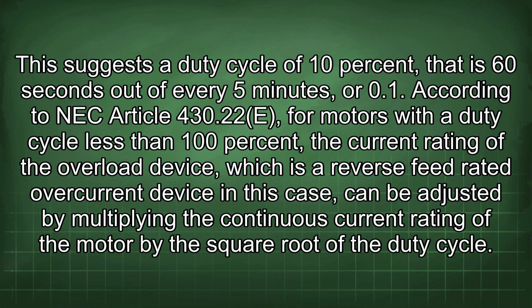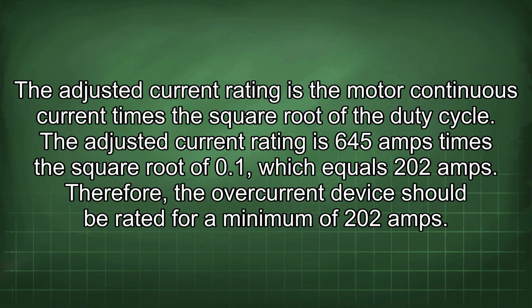430.22(E), for motors with a duty cycle less than 100%, the current rating of the overload device, which is a reverse feed rated overcurrent device in this case, can be adjusted by multiplying the continuous current rating of the motor by the square root of the duty cycle. The adjusted current rating is 645 amps times the square root of 0.1, which equals 202 amps. Therefore, the overcurrent device should be rated for a minimum of 202 amps.